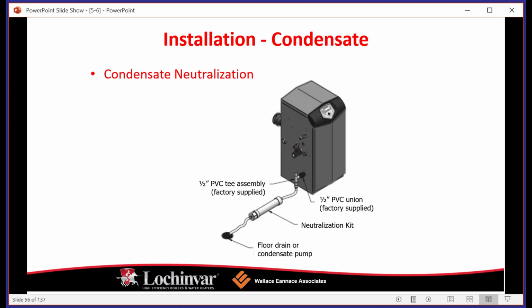The neutralization kits are not difficult to install, but they are important, okay? So as the boiler runs, again, we're capturing that latent heat in the heat exchanger. We're using that as energy to create efficiency, and one of the byproducts is that condensate. So you're going to have water, again, possibly a gallon per hour for 100,000 BTUs running out, and we need to dispose of that water. We need to get rid of it somewhere.